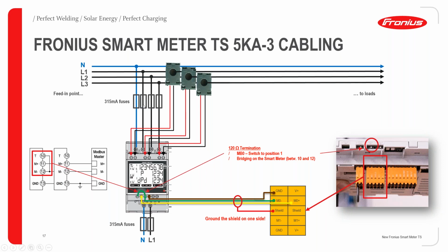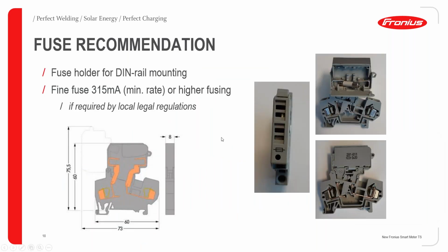And then these 315 milliamp fuses, these are optional. If your local regulation demands it, you can use it. Otherwise, it's not mandatory from your side. It's an optional one for you. And then there's a fuse recommendation. I don't think we are using it in the Scandinavian or Nordic countries, but if you are using it, then you can use the DIN rail mounting fuse holder. Then the minimum rating must be 315 milliamps, or you can use the higher fusing based on your cable's cross section. You can decide your fusing.